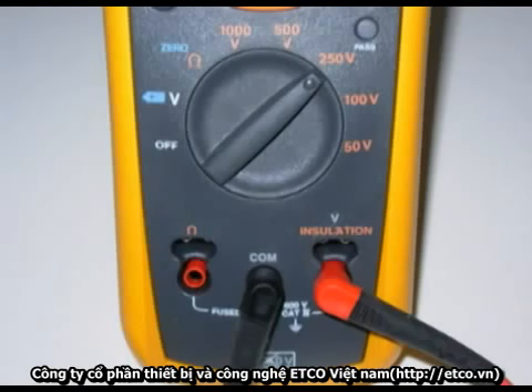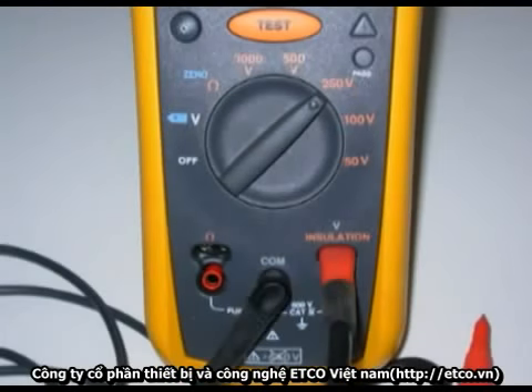I know there's a lot of confusion about what's a Cat 3 meter, what's a Cat 2 meter. In reality, the Cat ratings have little to do with the rated working voltage, i.e. 600 or 1000 volts, and more to do with meter protection from high transient voltages while testing. It's very possible to have a Cat 2 meter rated at a working voltage of 1000 volts and a Cat 3, or in this case even a Cat 4, rated at 600. But if there were an issue where you would have a very high transient voltage spike, that's where the higher Cat ratings come in. This is a shot of the remote lead plugged in.